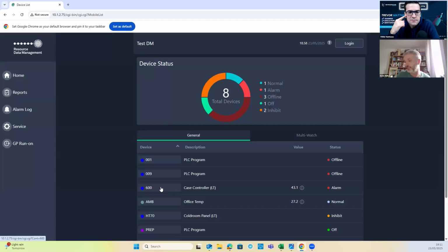So all I've done for that is I've gone into the controller network menu, and there's an option called ID. And it's a 3-digit number, and I've just picked any 3-digit number to put in there. If I had 50 cases to do in a store, I would do it very logically. I would start at number 1 if it wasn't in use, and I'd get to number 50, as you do. So RDM is brilliant for logging on new controllers. With many types of panel, you need to tell it what controller you're logging on and what address. With RDM, it figures it out for itself.